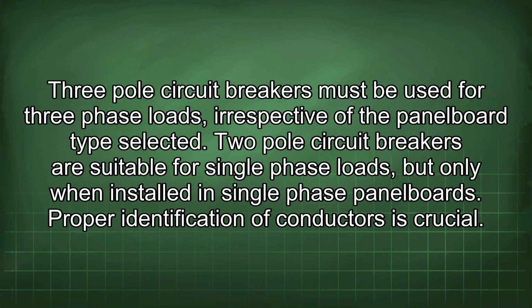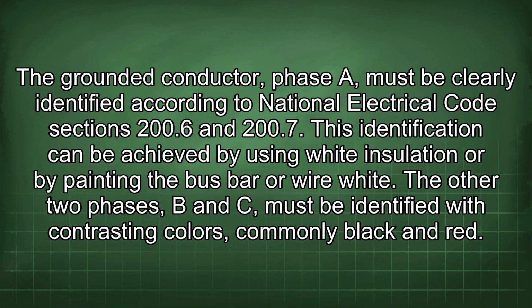Proper identification of conductors is crucial. The grounded conductor, phase A, must be clearly identified according to National Electrical Code sections 200.6 and 200.7. This identification can be achieved by using white insulation or by painting the bus bar or wire white. The other 2 phases, B and C, must be identified with contrasting colors, commonly black and red.